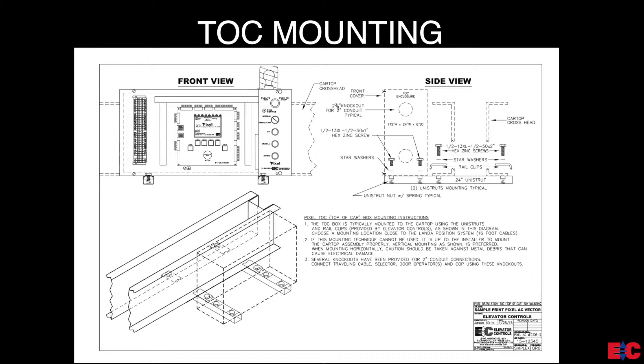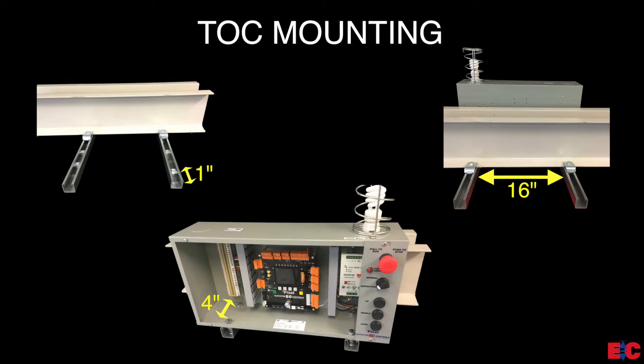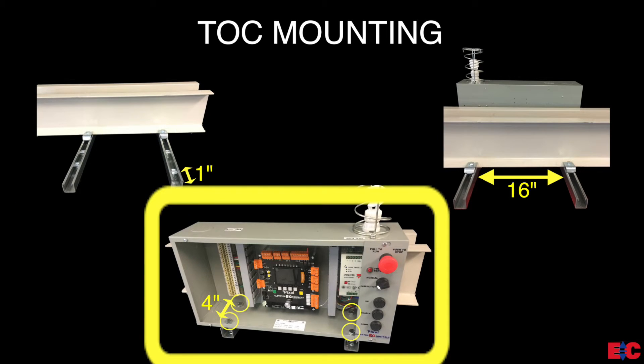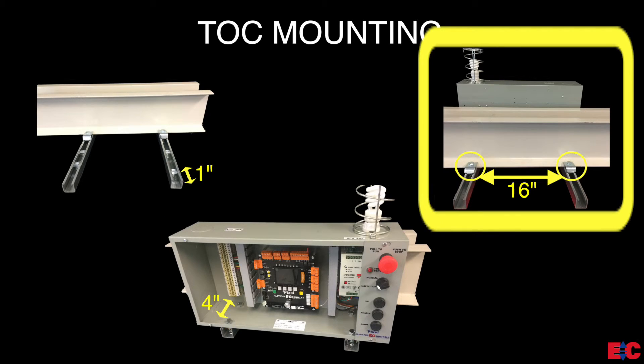Before we begin mounting the Pixel TOC box, go to page QR6 of the Pixel controller prints and review the detailed mounting instructions. Remember to keep in mind the location of the Pixel TOC box should be within a 16-foot reach of where you will be installing Landa. The following lengths should be taken into consideration: the one-inch gap from the front of the unistrut to the center of the first spring nut; the four inches between the center of the spring nut used to mount the Pixel TOC box to the two pieces of unistrut; and the 16 inches from the center of one unistrut to the center of the next.